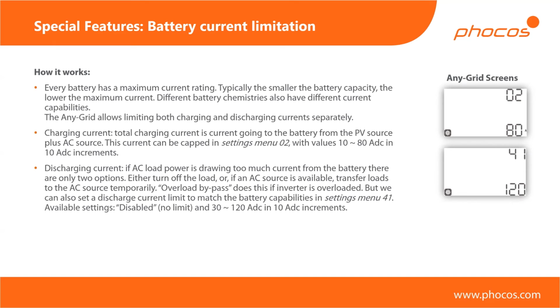This is just to ensure that your loads are always running, even if for some reason somebody turned on the 3 most powerful loads at the same time. So just keep in mind that this doesn't mean that you can put like 8 kilowatts of loads on your inverter and it doesn't matter if it just switches back to the grid 20 times a day. But even if it does, there's a timer, so it's not going to flick back and forth all the time. It's going to stay on the grid for several minutes and then come back if possible, if the power requirements have settled down.